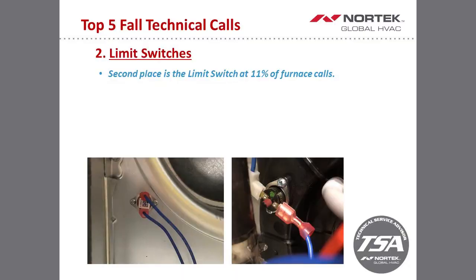The second most common call that we get in tech service is in regards to limits. Now, this can apply to anything from it being temperature related, along with maybe having a high ohm value on a limit switch where you could be getting a false limit code, along with the limit circuit potentially being grounded to the cabinet. If that's the case, most of the time it will not actually pop your 3-amp fuse. You'll end up getting a false limit code on the board if your limit circuit is grounded.